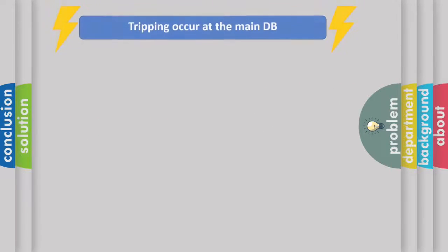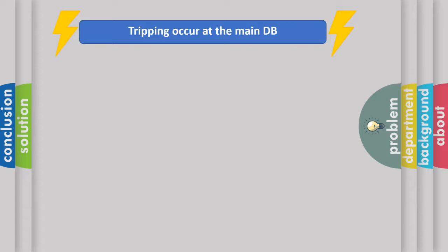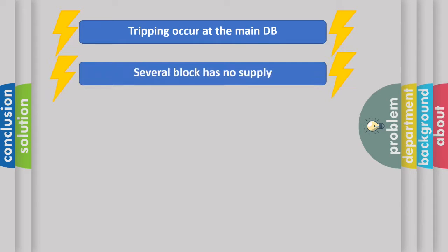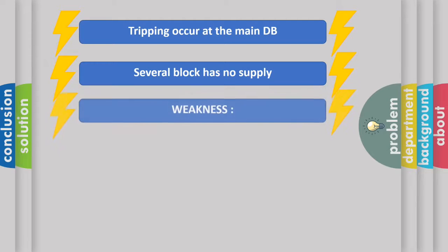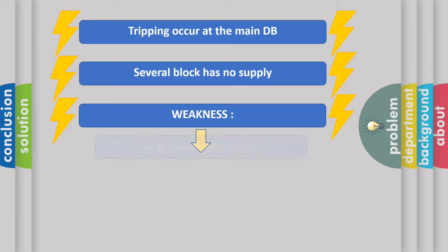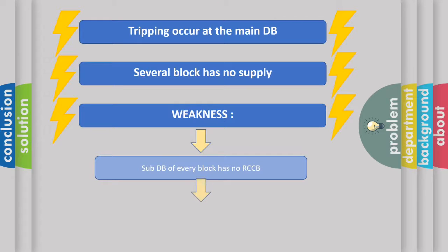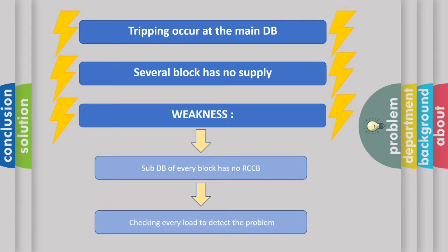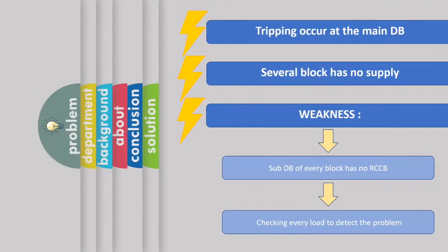The problem statement is tripping occur at the main DB of the school block. The tripping affects several blocks in the school, causes no supply. The weakness of the system is no RCCB were installed at every phase in main DB. It makes harder to detect fault in which block instead of checking load at every phase to detect the problem.